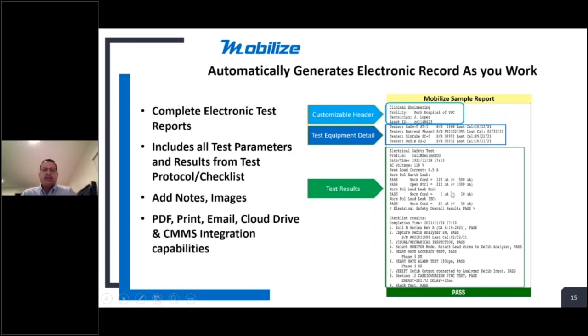It just came across. And then in parentheses, you have your actual standards, your test, your pass-fail limits that were designed by you, created by you. Here's what my pass-fail criteria is for these devices. And then you have an overall pass or fail for that bundle of tests. Then you have the same thing below that for all of the other checklist steps that we just ran through. It will list the individual steps that we were required to do, and it captures the information where data had to be captured as part of the service performed.